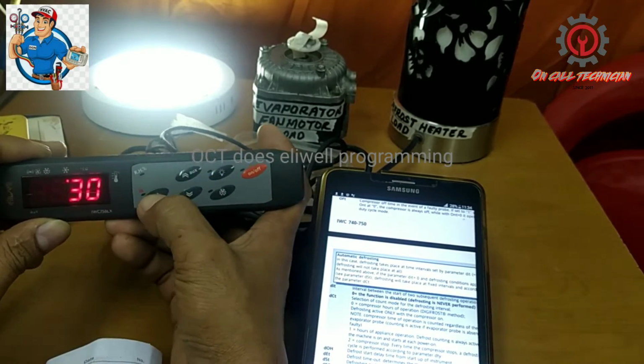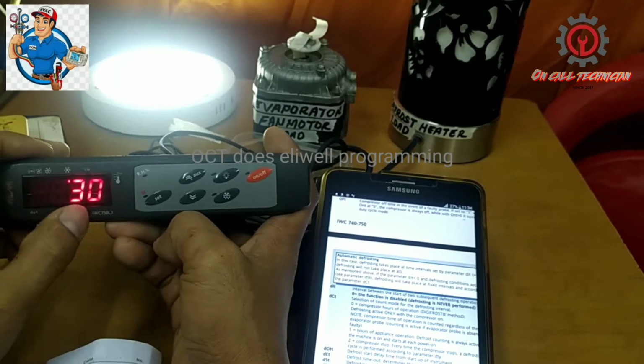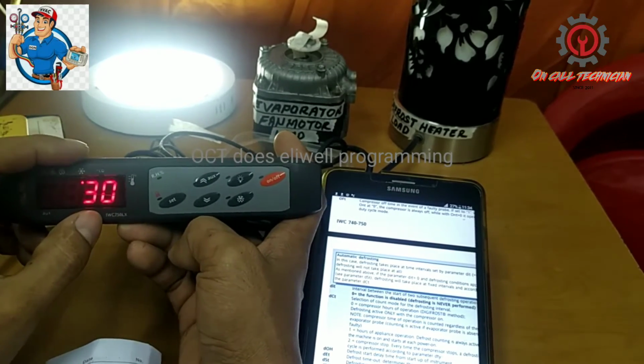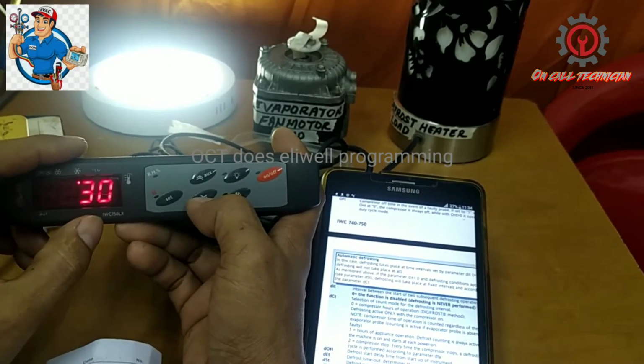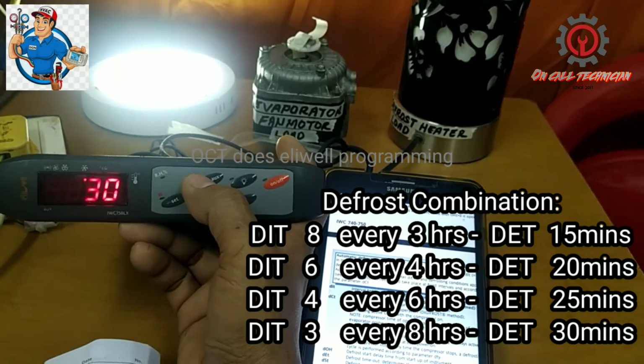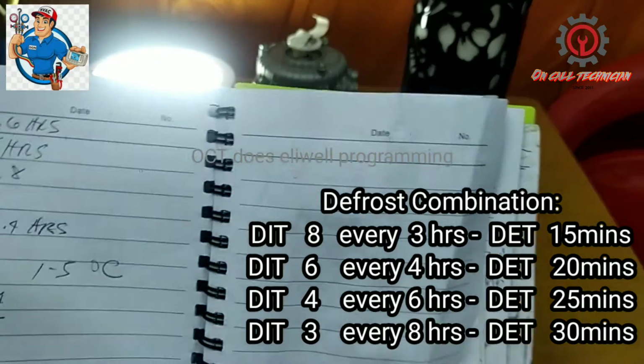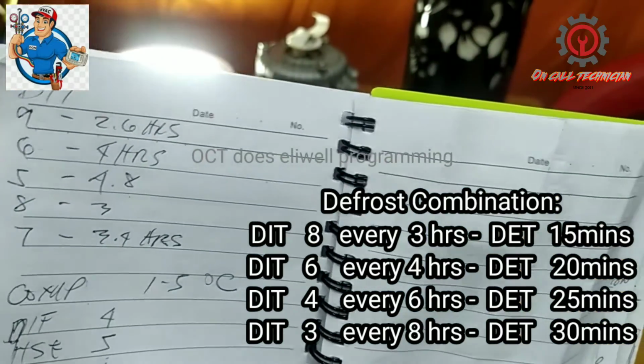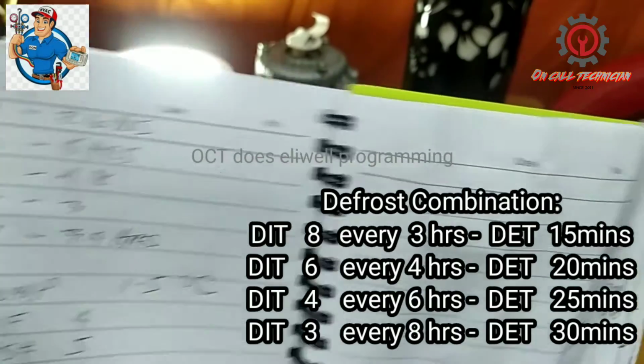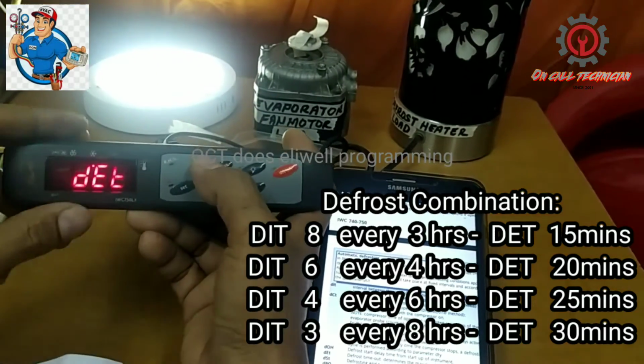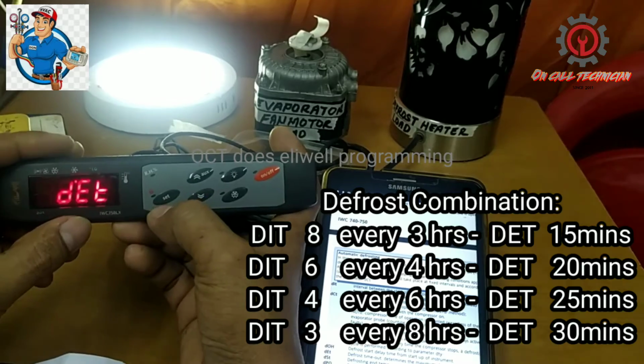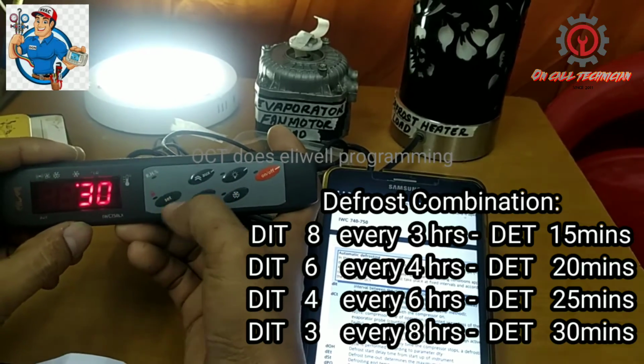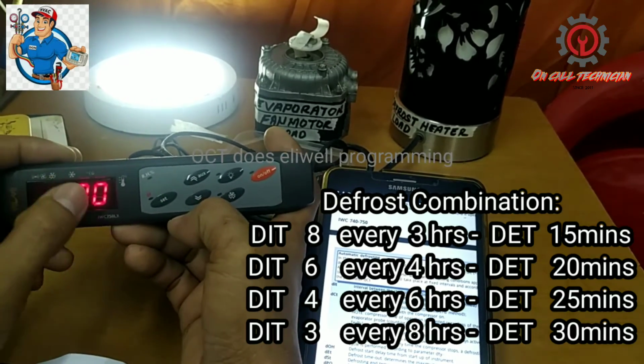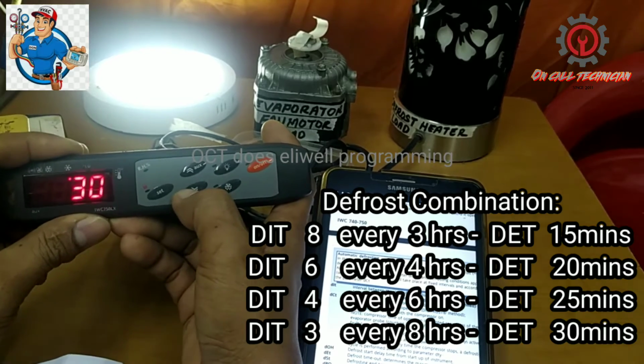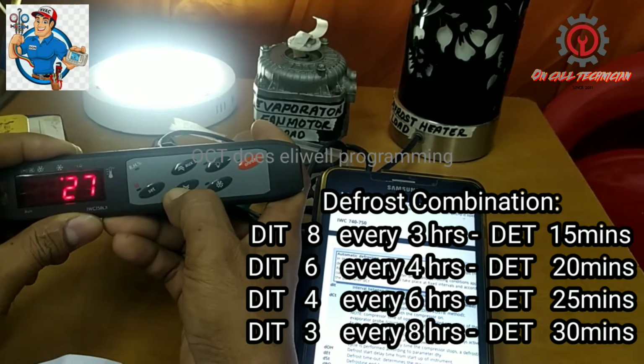Now the default value is 30 minutes. So if we set it to 6, which is every 4 hours, the defrost will engage, and if you want to reduce that one, you can do it.